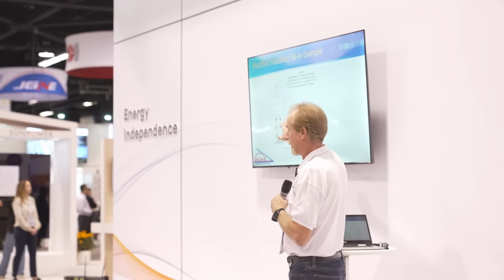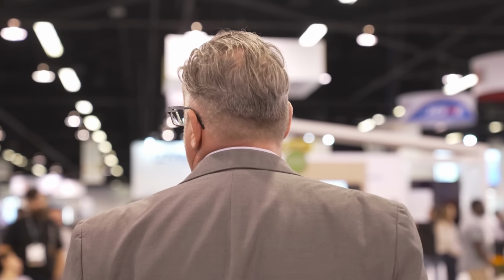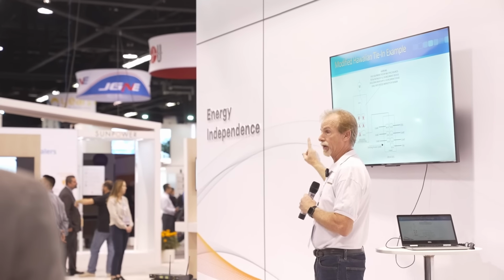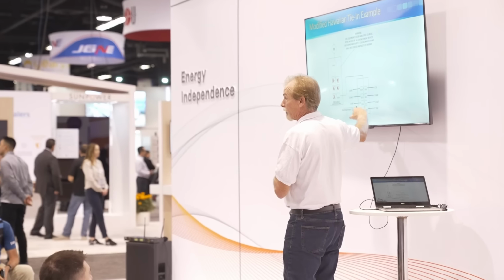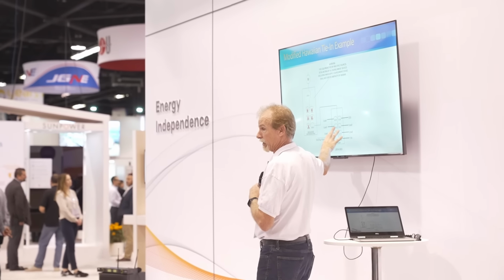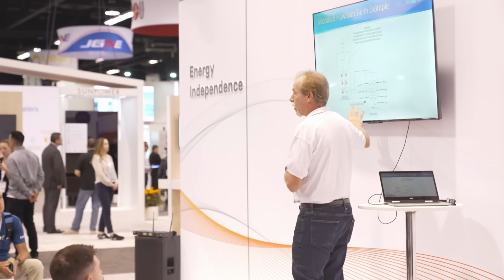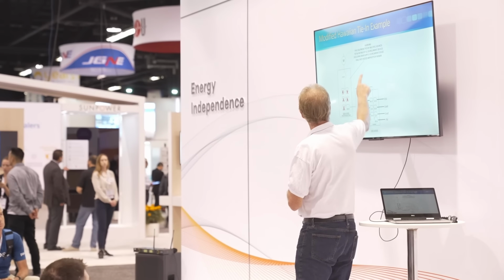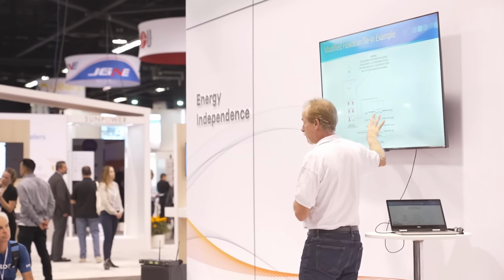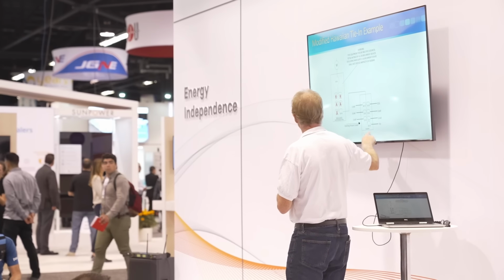Again, we have to put this warning label on there, but now we're using the sum of the breakers in this panel, including this guy, is no more than 100% of the bus bar rating. Okay, there's different rules, because we could put up to 30 breakers, maybe even 40 breakers in this panel, do all of our breakers, maybe add breakers to this thing. We're not under this limitation if we're doing the 100% rules. 100 plus 50 plus 50, that's 200. Everybody got that? It's really, really difficult math, I know.